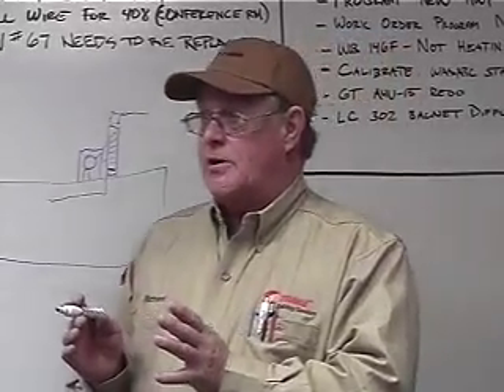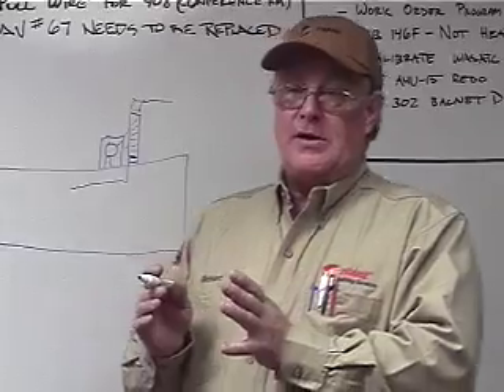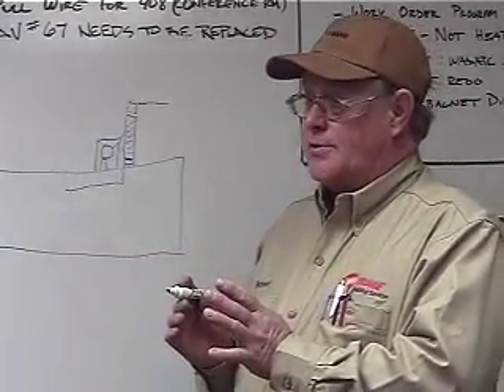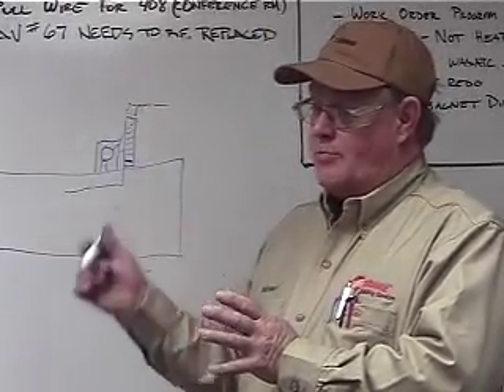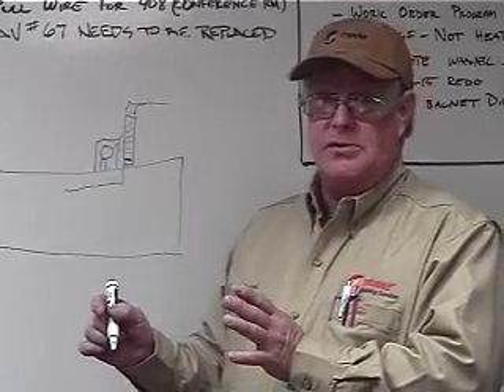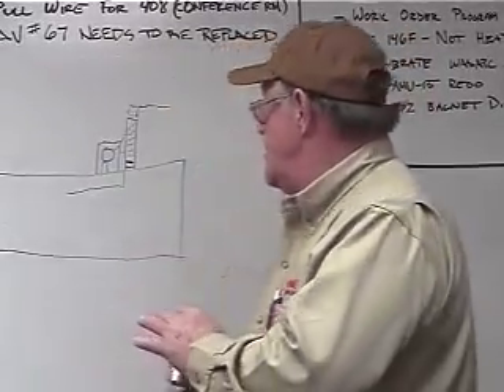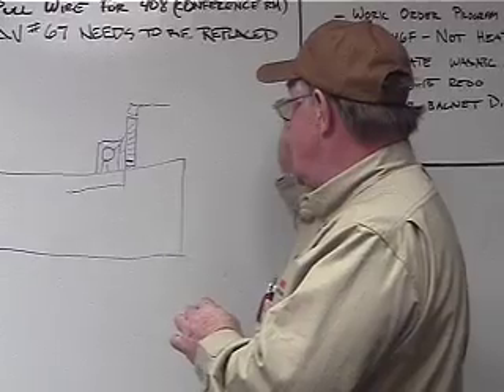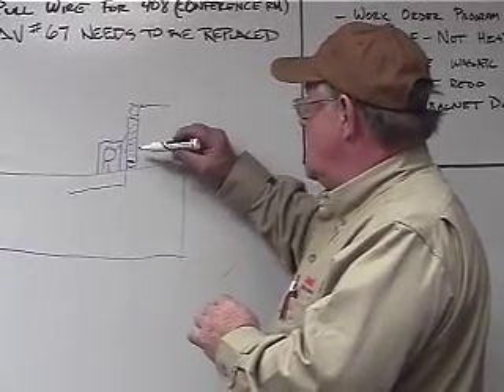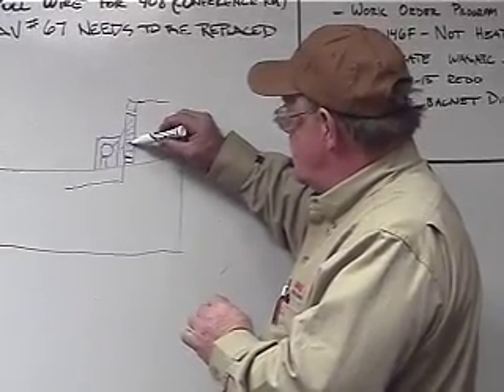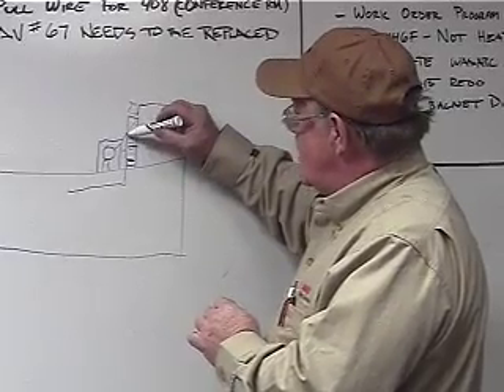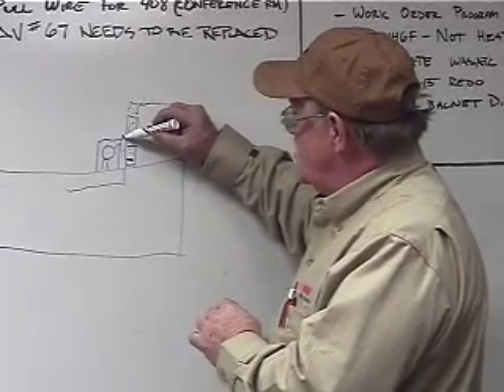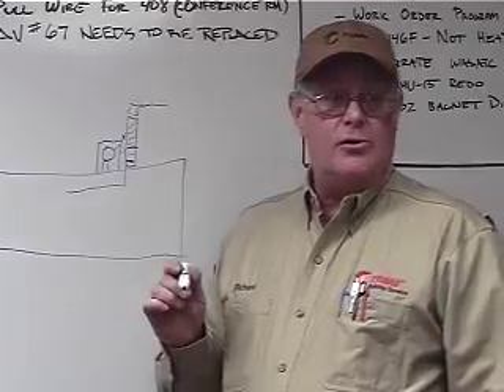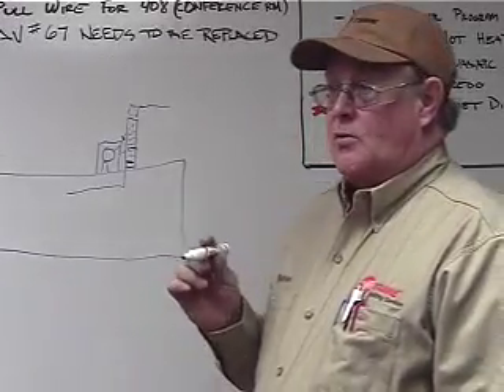There's a heating element in it that will boil off any of the refrigerant vapors in the charcoal and dump it back into the evaporator so we're not losing refrigerant. And then the non-condensables go out. As we lose our non-condensables, this refrigerant level is going to come up like this, and the suction temperature on that compressor is going to rise.